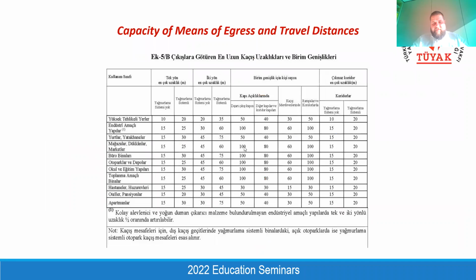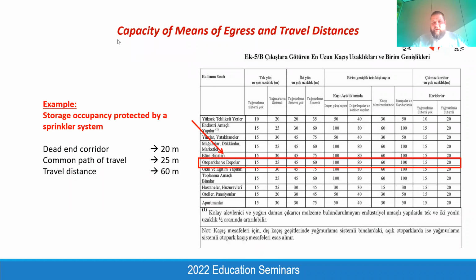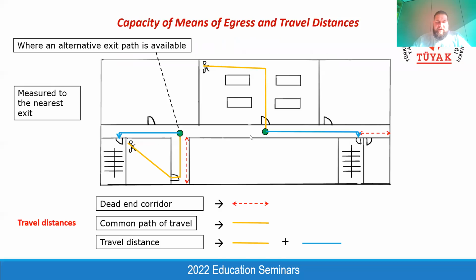It's a very limiting design criteria. That's the same for the dead end corridor length. For example, for the dead end corridor, it is 20 meters for the sprinkler building, and it's only 15 meters for the non-sprinkler building. And for the travel distances, it becomes 45 from 60. It's very challenging if you have only two staircases, and if you don't have a sprinkler system, probably you need to provide an additional third staircase for your building, for example, here.